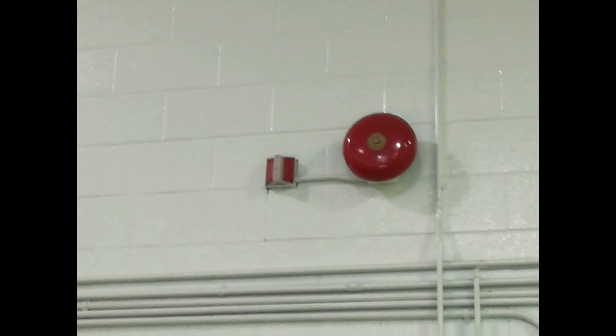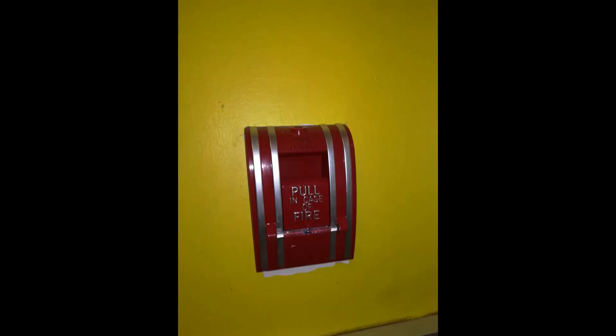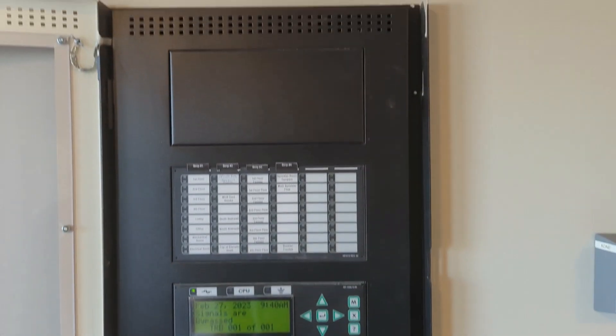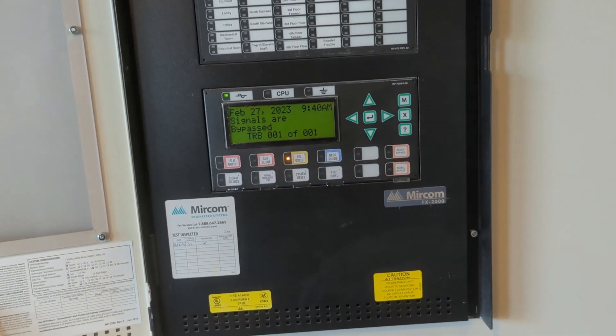So today, I'm going to kick things off by making a video of a Mircom FX2000 at a condo building. We're testing two of these. What we are testing is elevator homing, elevator recall, and the top of the shaft smoke detectors. I am at the panel for this video, which is kind of boring. This is what I'm working on today — FX2000, doing the elevator recall.